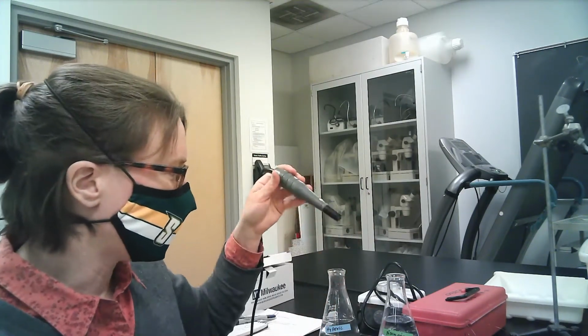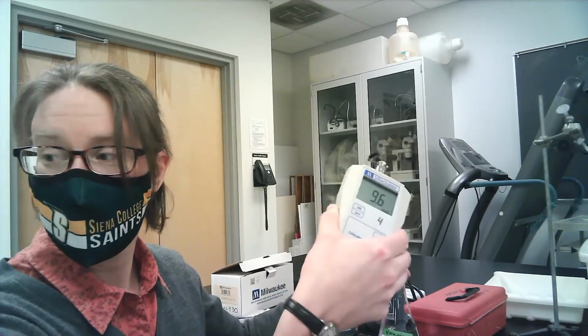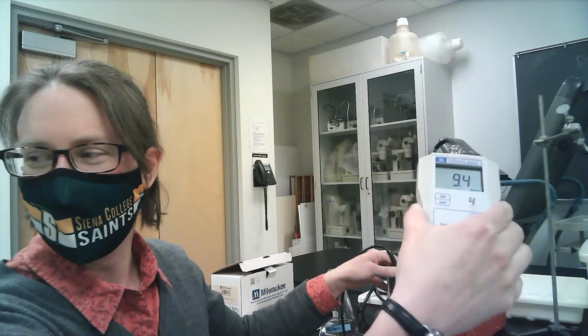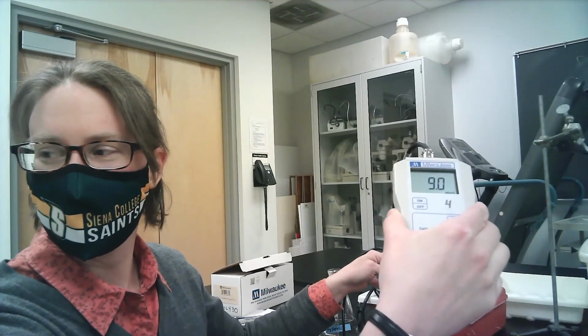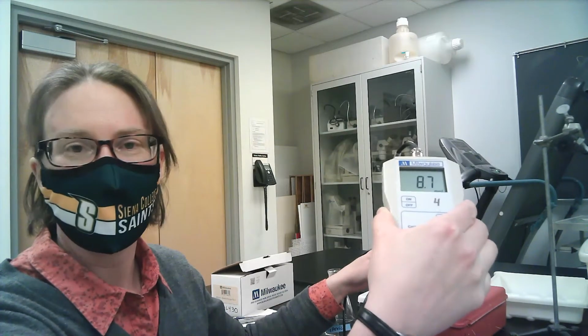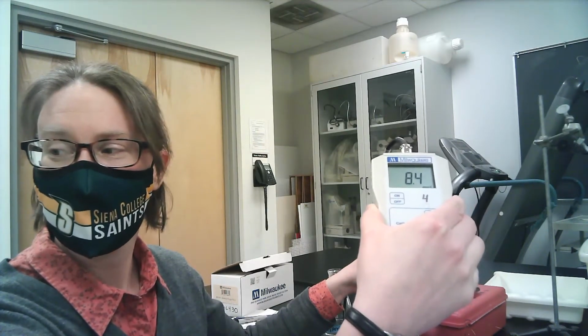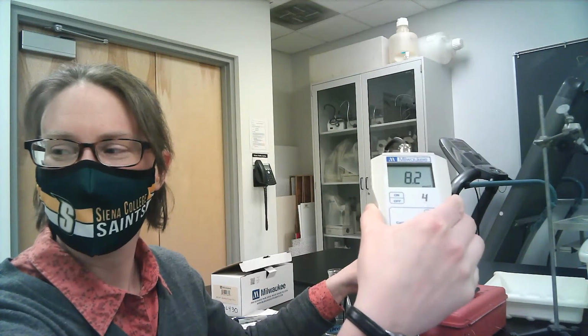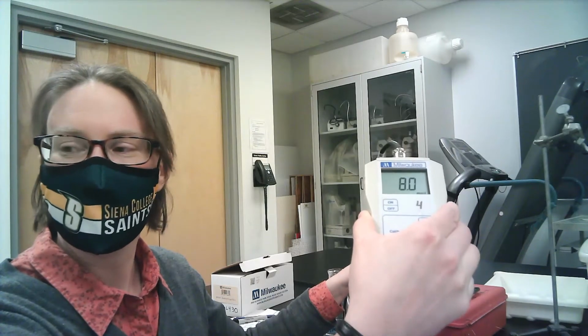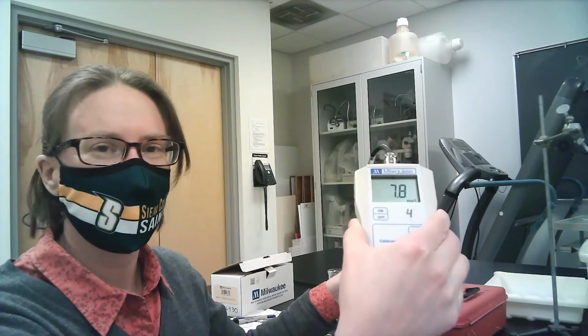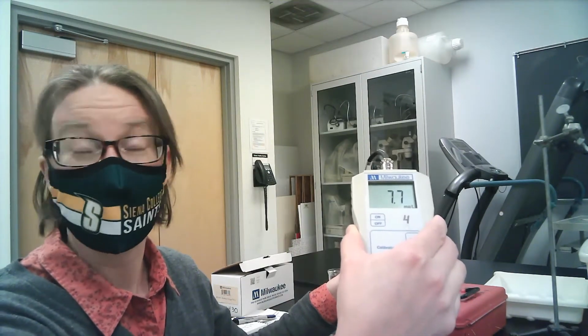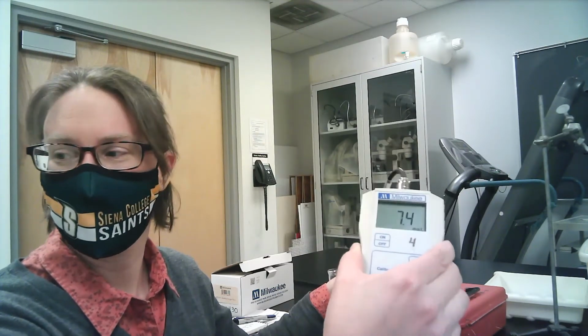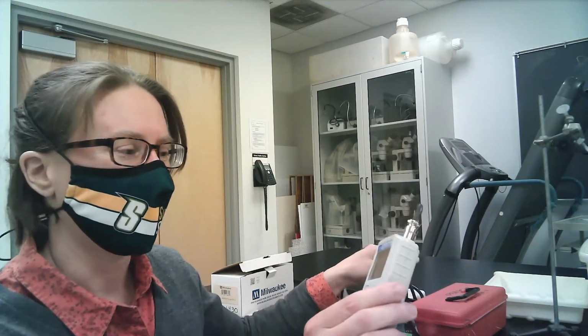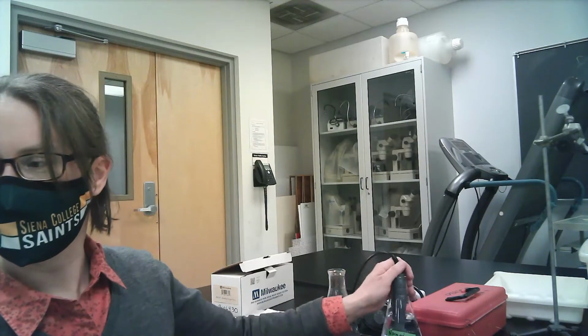When you're ready to measure the oxygen content of your solution, all you need to do is put that into your solution, and you'll notice here that it's starting to tick down. It may take a minute or two to reach a point where it will settle. Looks like we're getting close. So just be patient with it. Wait until it settles. It actually uses oxygen as part of its sensing mechanism, so it may not completely settle. You just want to wait until it reaches a relatively stable reading. You're going to take that reading, and that's going to be in milligrams per liter. Okay, so that's my normoxic solution here.